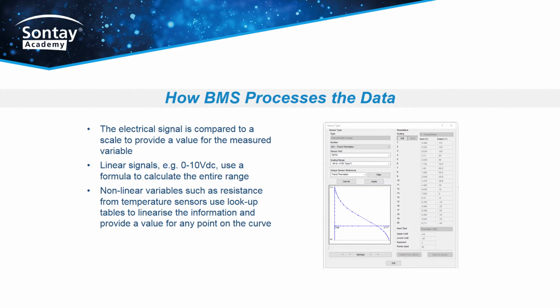Different BMS controllers require you to set this up in different ways, but the result is always to provide as accurate a value as possible based on the resistance measurement. The more points you define in a lookup table, the more accurate your readings will be across the entire sensing range.